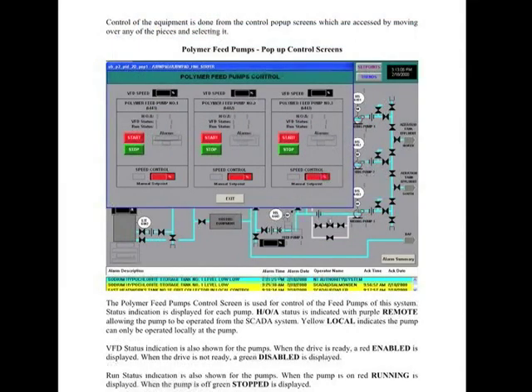On the polymer feed pumps, you have start-stop controls, you have speed controls. It gives you the status of the hand-off-auto, the VFD, which is always going to show either enabled or disabled, and the run status, running or stopped. You also have alarms here that will show up if there's a problem. They are, I believe, fail to run and overload or fault, which are basically the same thing in this case.